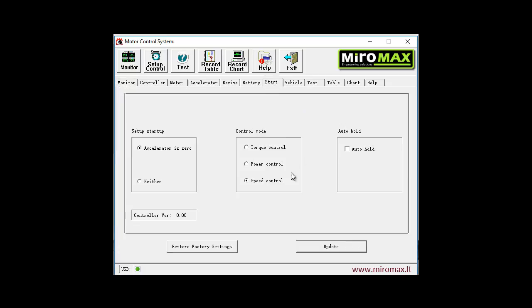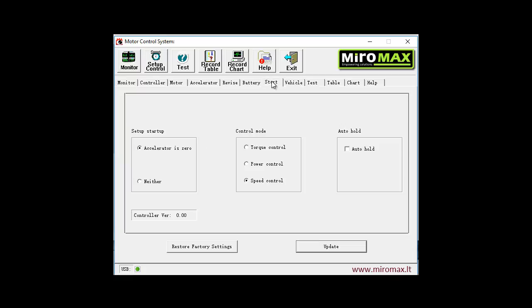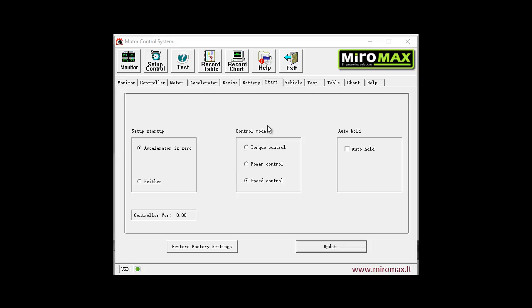Now about actual parameters. The most important of them is control mode. Here we can see three options which select motor control mode: torque control, power control, and speed control. This defines what actual parameter is proportional to the speed throttle signal - either torque, speed, or power as a combination of the previous two.